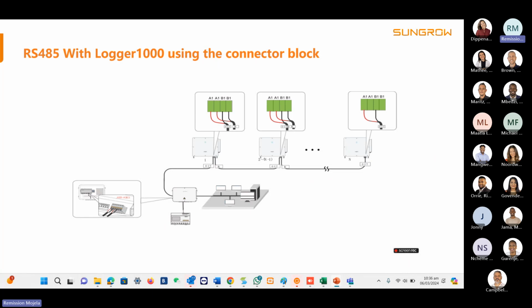And then with the Logger 1000, with RS485, with the Logger 1000 connector block, from each and every inverter there's A1, B1, A1, B1. So the A1, B1 is common, but we make it easier to have 2 ports so that you have in and out, in and out, in and out, in and out. So directly from the Logger 1000, you'll go to the out of the inverter, and from the out of the inverter, you'll go to the next inverter. That's basically how your daisy chaining is going to be. And then the meter will be sitting on a different port, like I said previously, and the inverters will be sitting on a different port on the Logger 1000.